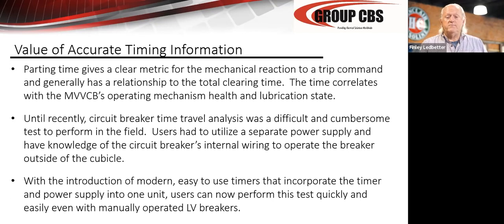Accurate timing is very important. Without accurate timing, you don't know what the speeds are. You don't know if the breaker will actually do its job. There are insulation tests. There are vacuum integrity tests. There are tests that test the pressure inside the vacuum interrupter. The timing test actually gives you the best reflected relationship to the health of your mechanism.